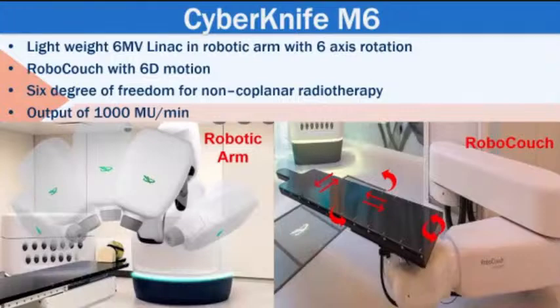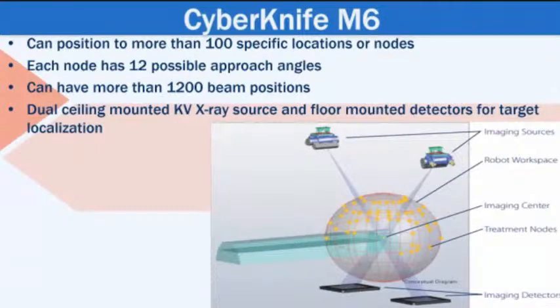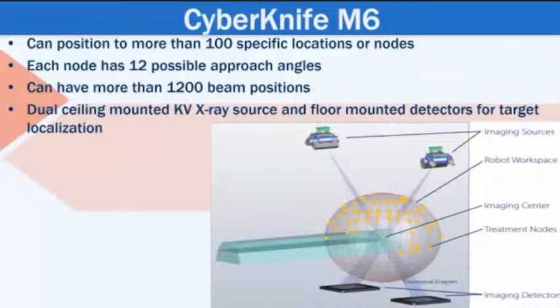The lightweight 6 MV linear accelerator with output of 1000 MU per minute is directly mounted on a robotic arm in the CyberKnife system, with 6-axis rotation to deliver the high-energy X-ray for non-coplanar radiation therapy. Moreover, the RoboCouch system provides a flexible 6-degree motion for patient positioning. The robot moves around the patient to deliver radiation. It can position to more than 100 specific locations, or what we call nodes. Each node has 12 possible approach angles, and therefore it can potentially have more than 1,200 unique beam positions.